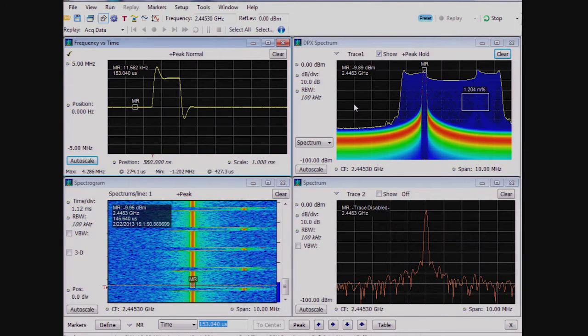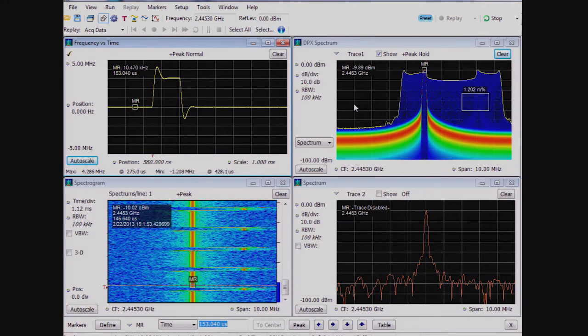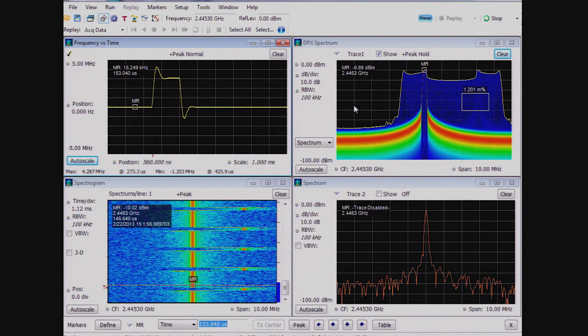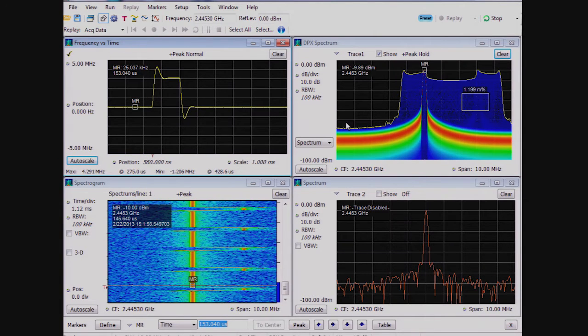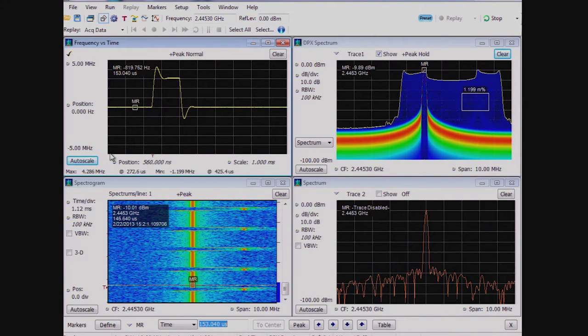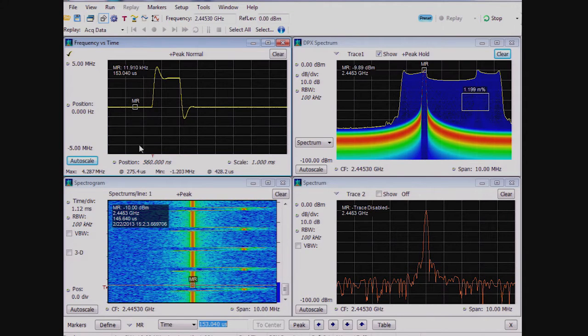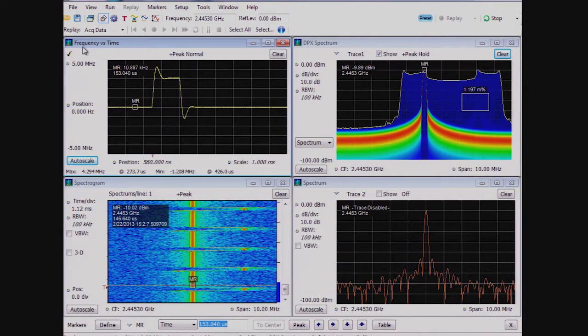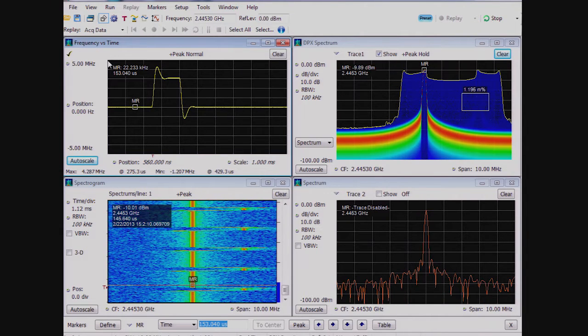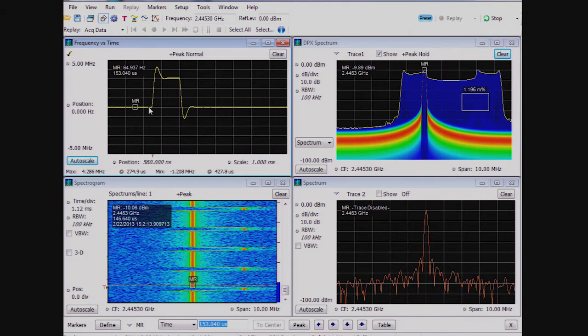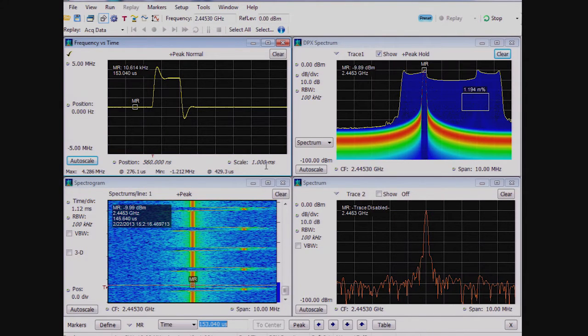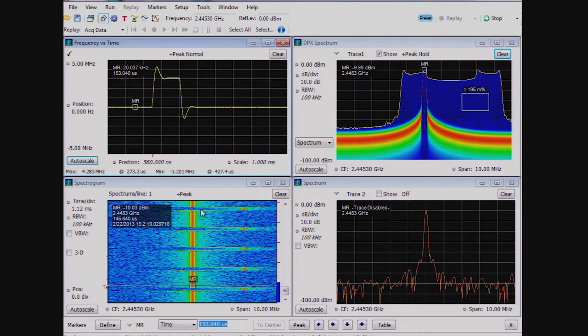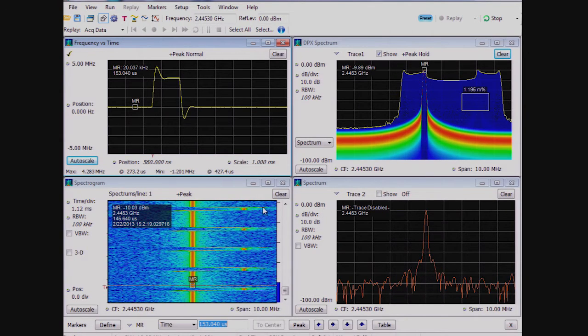Now, with some adjustments, we can show the complete transient. We are looking at the DPX spectrum display that is still running, but upon each DPX density trigger, the instrument is capturing and analyzing one millisecond of signal data. The other displays shown are the frequency versus time display, which has the frequency relative to the instrument's center frequency on the vertical axis versus the capture time shown on the horizontal axis. The spectrum and spectrogram displays are also shown.